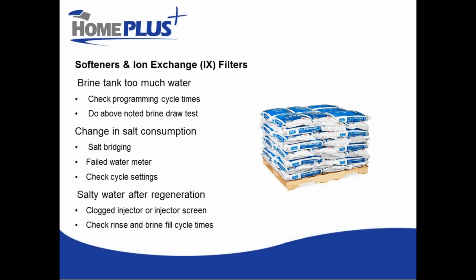So definitely worth doing. Too much water in the brine tank, if it's higher than what it normally is, is usually a sign that some sort of problem is starting. So when you go to add salt to your brine tank, if the water level looks unusually high, you probably have an issue there.